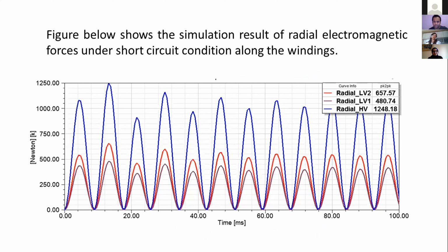The figure below shows the simulation result of radial electromagnetic forces under short circuit condition along the windings of the transformer. According to the simulation result, the radial force in the high voltage winding is calculated at about 1,248 kilonewton, where its value is lower, 480, in the inner LV winding and 657 in the outer LV winding.